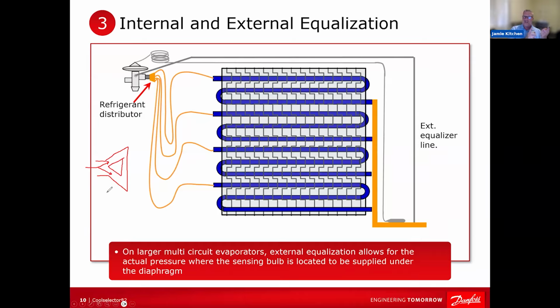So if the TXV thinks it's 45 degrees, it needs 7 degrees of superheat. That's 52 degrees. But if it's only 35 degrees in there, it's going to need 17 degrees of superheat to open up. And so you're drastically going to underfeed the evaporator.